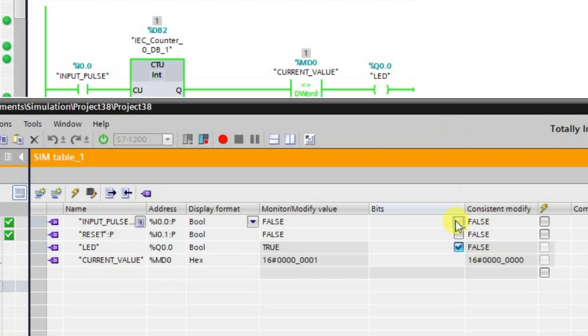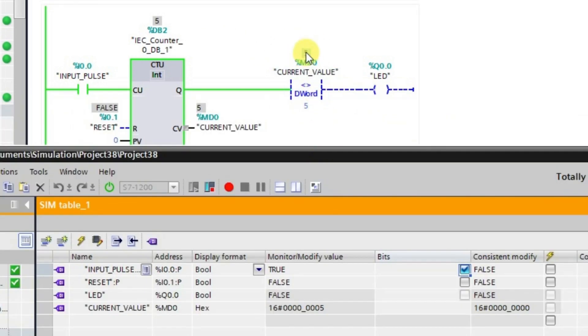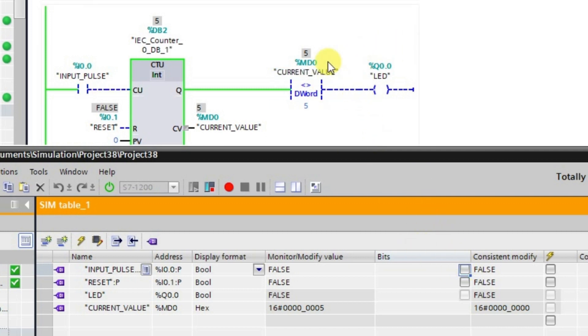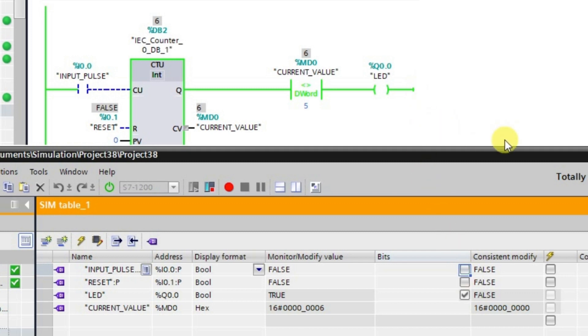Giving pulses while monitoring, when the value is 4 the output is still high. On the next pulse the value becomes 5 — both values are equal and the output drops to the low state. Giving one more pulse, the current value becomes 6 which differs from the preset of 5, and the output returns to the high state. This confirms how the not equal to comparator behaves.